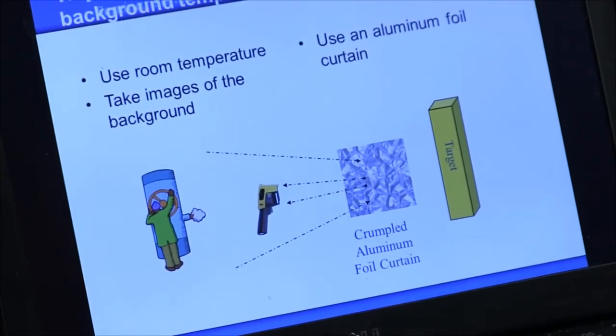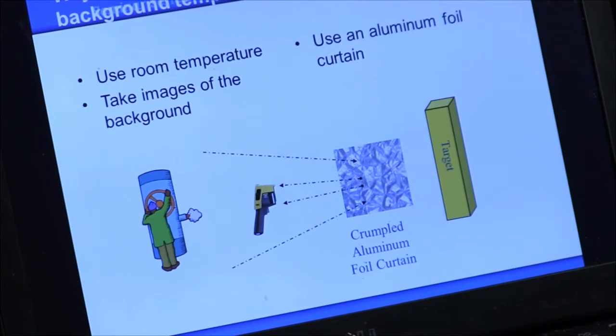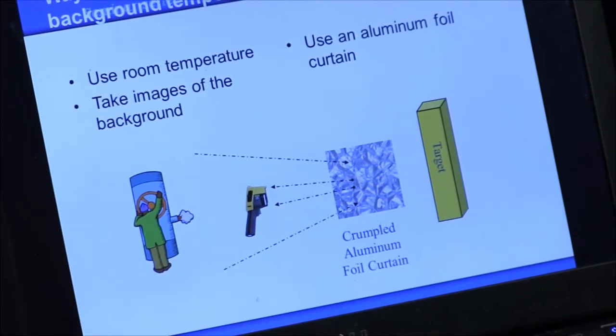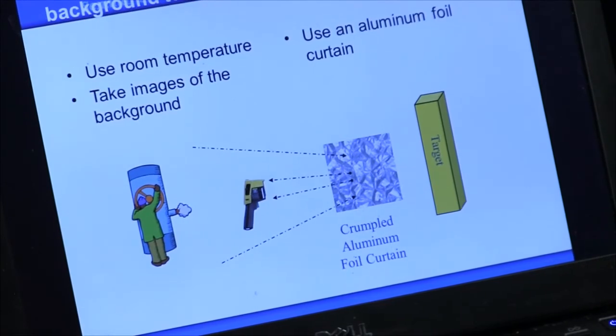For the background temperature, first we can use the room temperature if you're not quite sure. You can take a sheet of paper and hang it up, then take the temperature of the paper after it's been there for a while. Another method is to take a background image of one of the walls if it's been at a stable temperature.